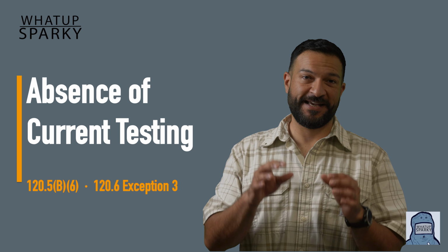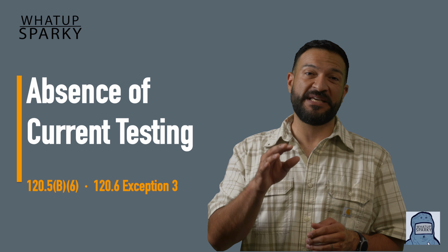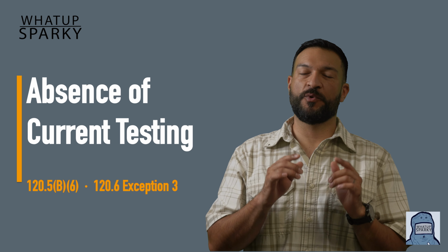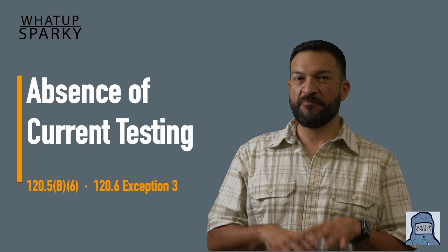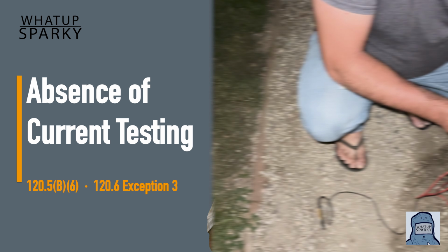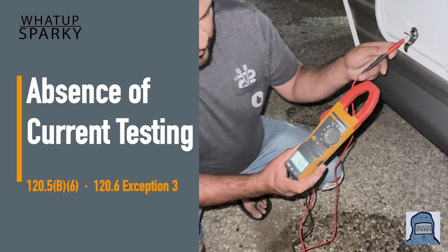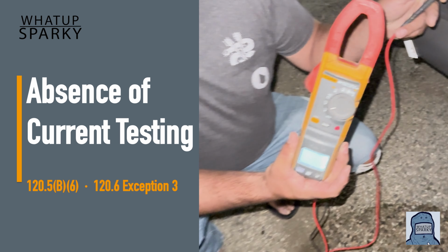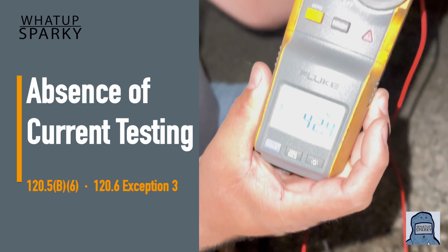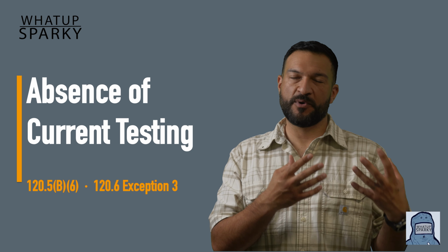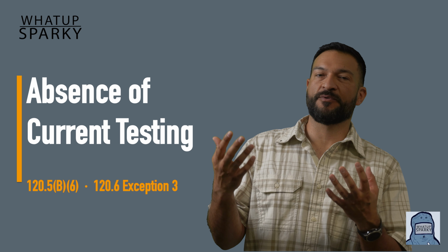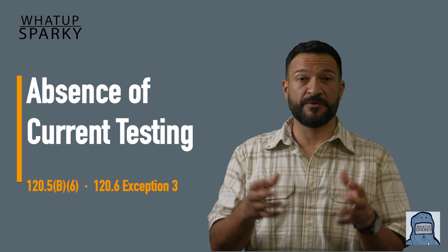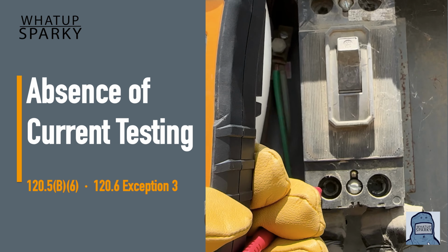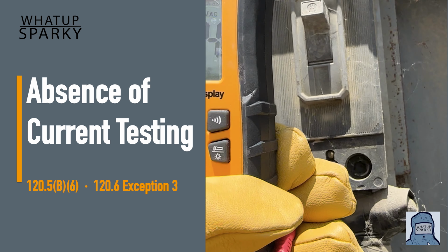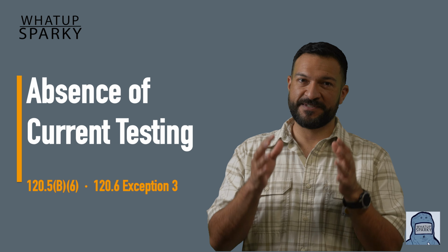Absence of current testing, 120.5B6 and 120.6 exception 3. Brand new requirements. When absence of voltage testing alone doesn't confirm that a circuit is de-energized, like in current-driven circuits or motor circuits with regen or maybe transformer secondaries or shared neutrals, you now have to use additional testing methods, including testing the absence of current.